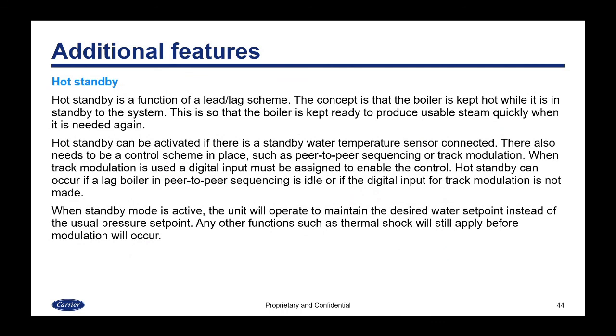Hot standby is available, and that's a function of a lead lag scheme. The concept with hot standby is that the boiler is kept hot while it is in standby to the system. This is so that the boiler is kept ready to produce steam quickly when it is needed again. Hot standby can be activated if there's a standby water temperature sensor connected. That's the first requirement. There also needs to be a control scheme in place, which is the second requirement, and that can be peer-to-peer sequencing, which we'll go over in the next couple slides, or track modulation from a BMS.